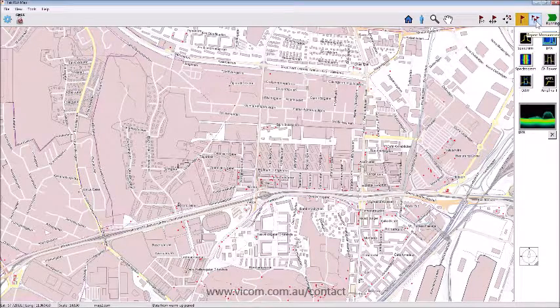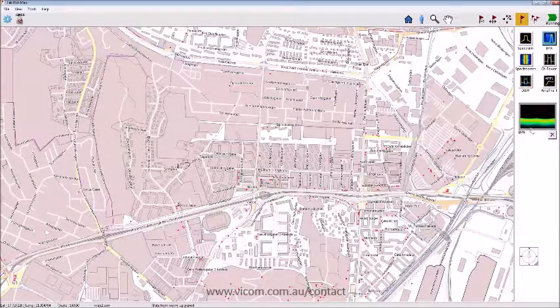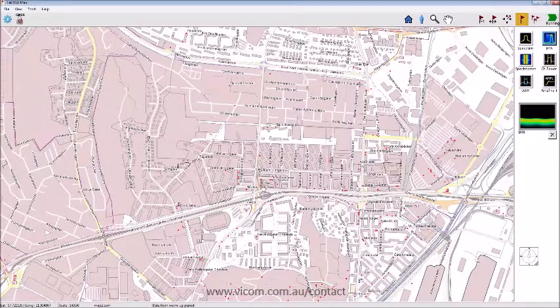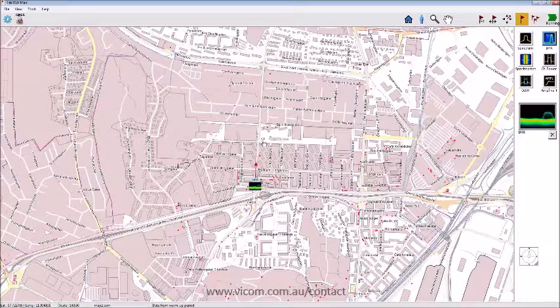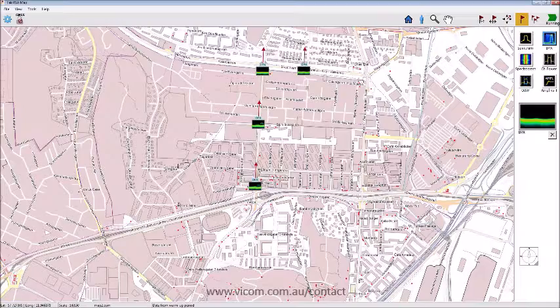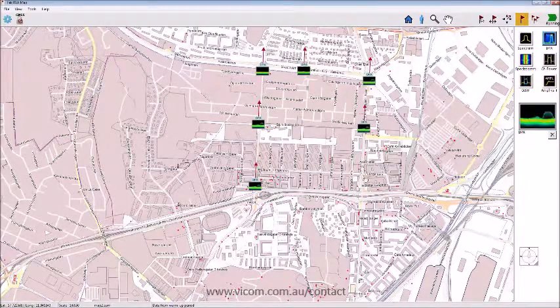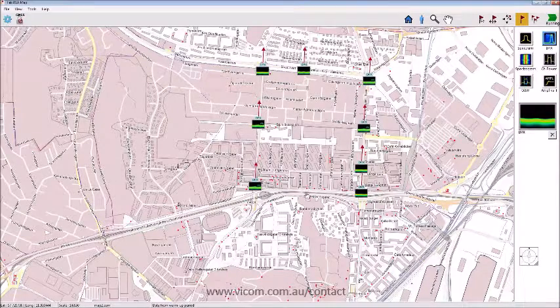In this demo I'm in my office without GPS or an automatic azimuth antenna, so bear with me. If you had GPS, you could do repeated measurements in a drive-by — just drive around the block, point the antenna, and check for interference. We'll walk and press the flag button to begin taking measurements.